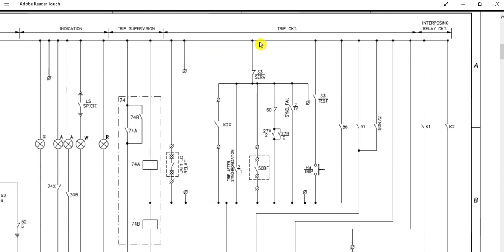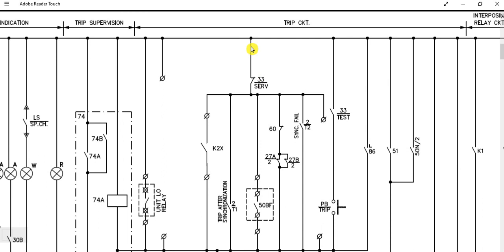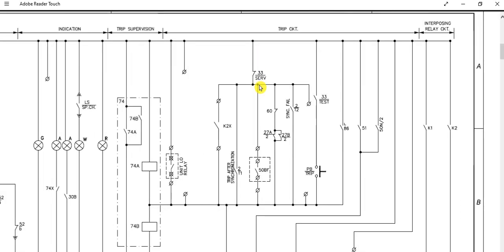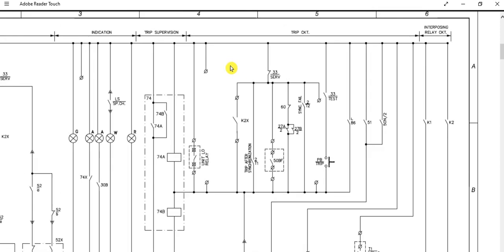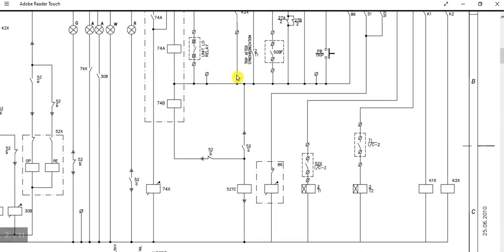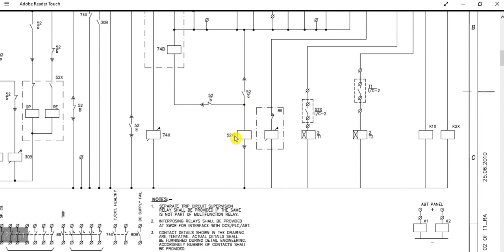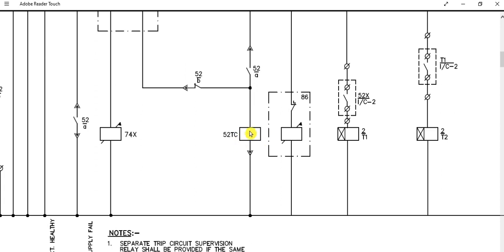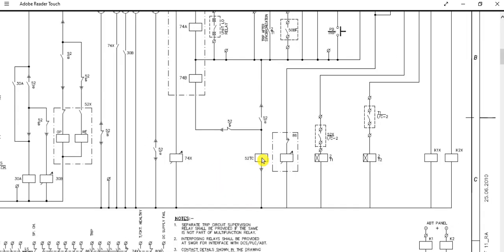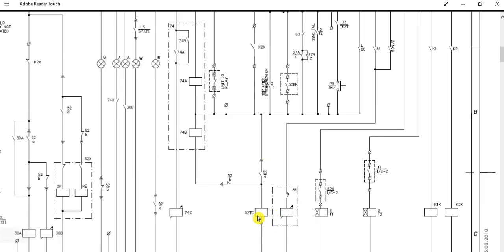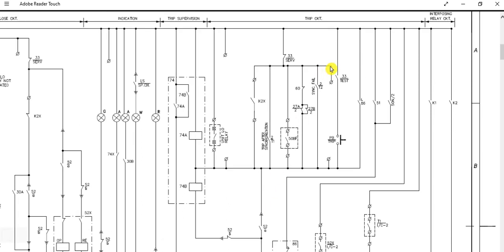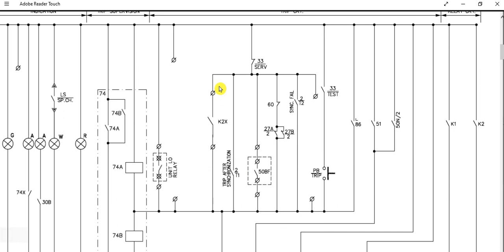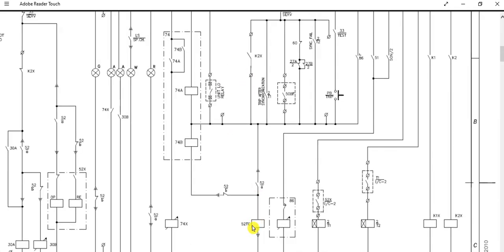Let's start. Suppose the circuit breaker is in service position. When will it trip? When will the trip command be issued? That is the purpose of this trip circuit. Here is the trip coil 52 TC. Our intention will be to energize this trip coil so that the contacts related to this trip coil will be triggered and the circuit breaker will be tripped. There are parallel combinations — any one of the parallel paths if activated will energize the 52 TC coil and trip the breaker.